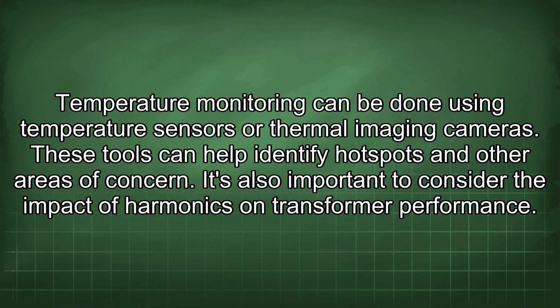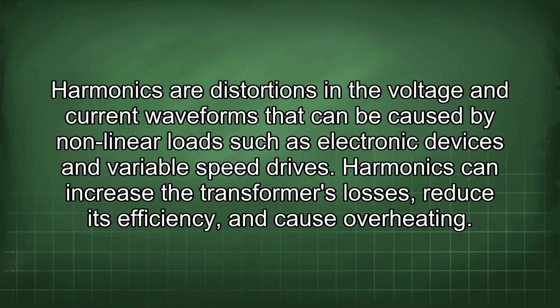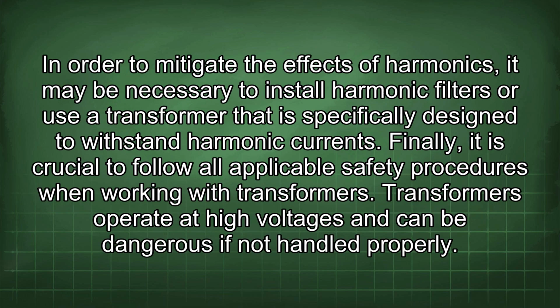It's also important to consider the impact of harmonics on transformer performance. Harmonics are distortions in voltage and current waveforms that can be caused by nonlinear loads such as electronic devices and variable speed drives. Harmonics can increase the transformer's losses, reduce its efficiency, and cause overheating. In order to mitigate the effects of harmonics, it may be necessary to install harmonic filters or use a transformer that is specifically designed to withstand harmonic currents.